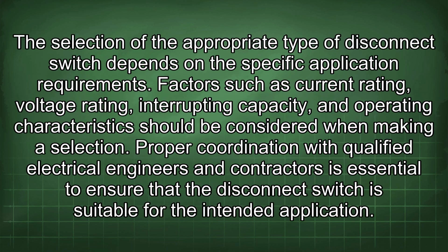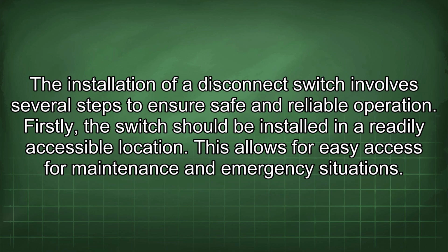The selection of the appropriate type of disconnect switch depends on the specific application requirements. Factors such as current rating, voltage rating, interrupting capacity, and operating characteristics should be considered when making a selection. Proper coordination with qualified electrical engineers and contractors is essential to ensure that the disconnect switch is suitable for the intended application. The installation of a disconnect switch involves several steps to ensure safe and reliable operation. Firstly, the switch should be installed in a readily accessible location. This allows for easy access for maintenance and emergency situations.